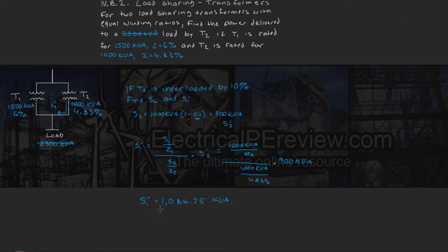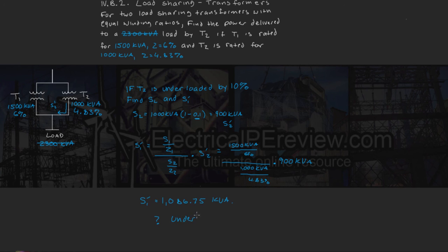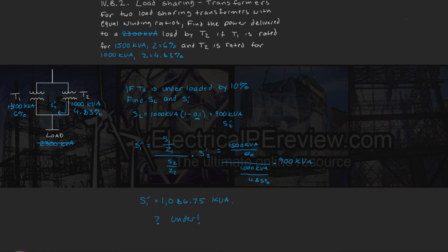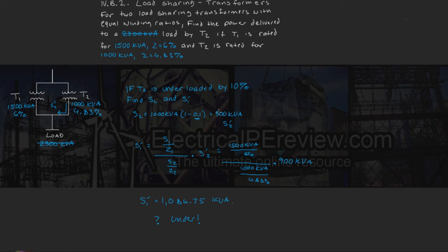Is transformer 1 underloaded or overloaded? Transformer 1 is underloaded. And that's because 1086.7 kVA is less than its rating of 1500 kVA. We already know that transformer 2 is underloaded because 900 kVA is less than its rated of 1000 kVA.